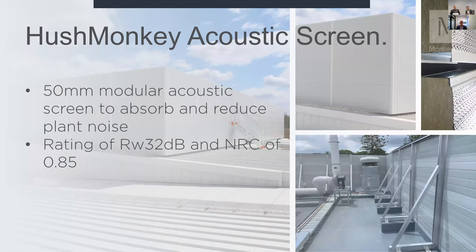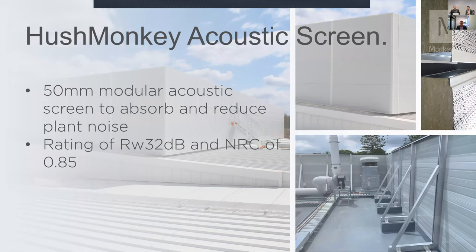Hush Monkey is our solution for acoustic screening, which not only blocks and hides the unsightly plant on the roof but also provides acoustic attenuation properties. It uses the same support structure as the louvre screening, with our Hush Monkey 50mm modular sandwich panel attached to the face. It blocks 32 decibels of sound that hits it, and has a noise reduction coefficient of 0.85, absorbing 85% of sound that hits it. It comes standard in surf mist colour but can be done in pretty much any colour. It can be integrated into the platform or provided as a standalone screen mounted to plinths or a concrete roof.